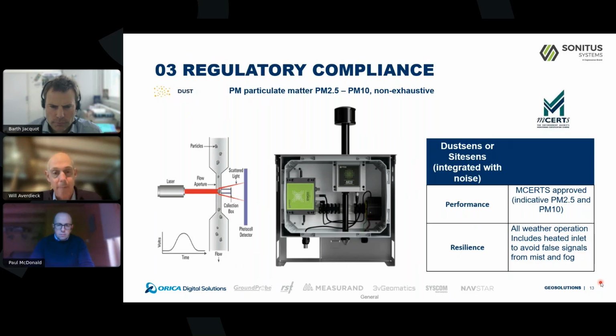Now, that section above the enclosure plays a very important part because it's a heated inlet. With optical particle measurements, as we know, the reason we see clouds in the sky is that clouds or water vapor will scatter light. So we don't want to have an interference from mist or fog. And actually, when relative humidity is greater than 60%, particles actually grow. So it's very important to control RH and make sure there is no interference from these water vapor issues. So we have a heated inlet. That's very important in any external use of particulate monitors.